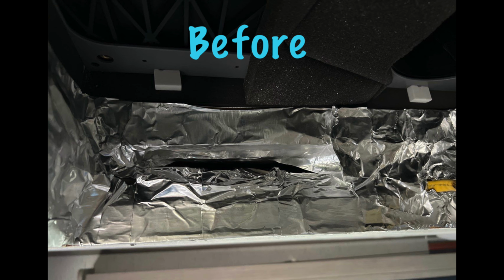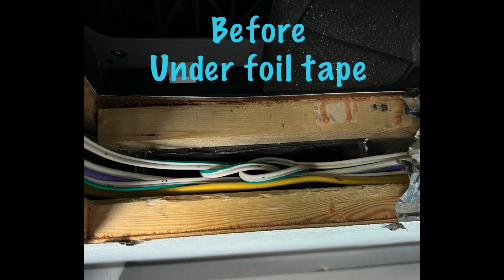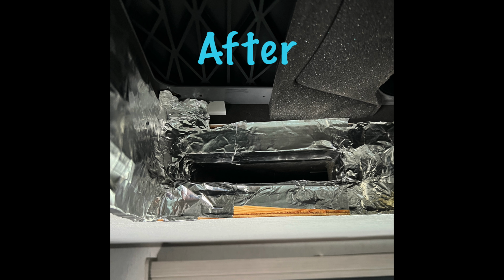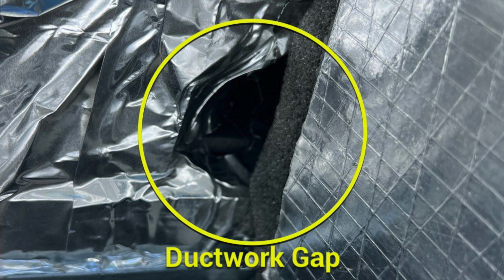If you look up inside of here, you can use a flashlight on your phone, look back in there to make sure things are open and clear. If a ductwork broke down over time and it collapsed, it can block the airflow and restrict things. That's a little bit more work, but it's definitely fixable. And while you're up there, you might see some loose foil tape and gaps in the ductwork. So if air is blowing through the ductwork into the attic cavity, it's not blowing into the room where you want the cold air. If you seal those areas up with some foil tape, it can easily take care of the problem. Now let's go look at a different style of filters and ductwork, different than this style, so you can see what else you can look for.